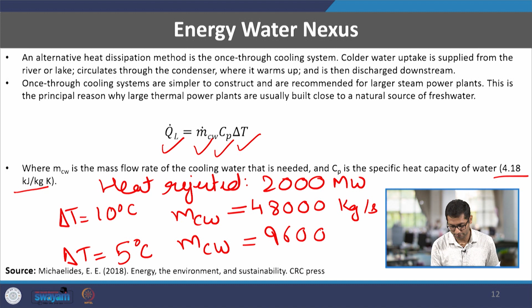Further, if this delta T is assumed to be around 5 degrees Celsius -- since we don't want to raise the water temperature too much -- this same mass flow rate would almost double to around 96,000 kgs per second. So you'd see a significant increase in the amount of water consumed to absorb the same amount of heat. This raises the question of whether we should be using such large amounts of water for these applications, and it's also the reason you'll find most big power plants located near some kind of fresh water source.